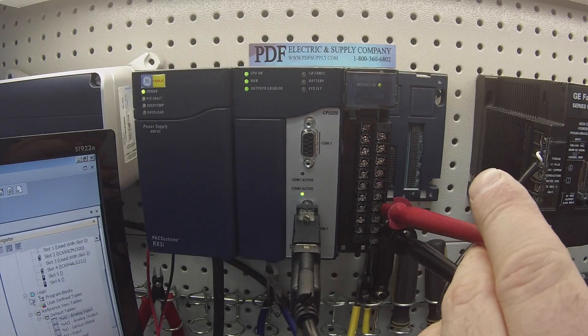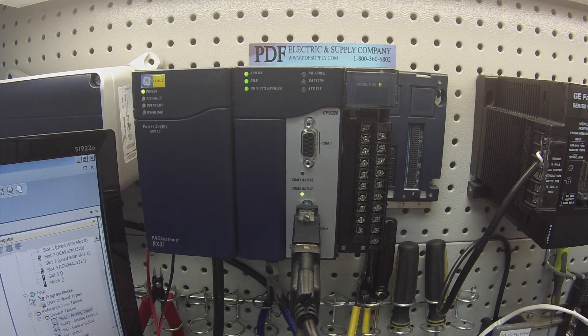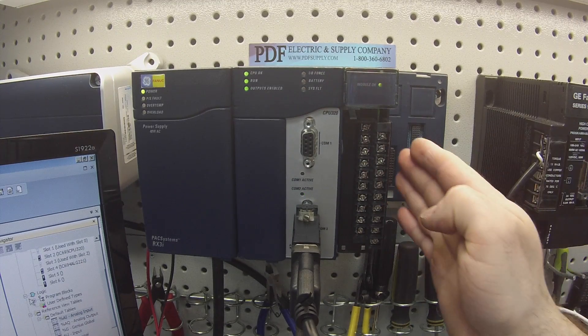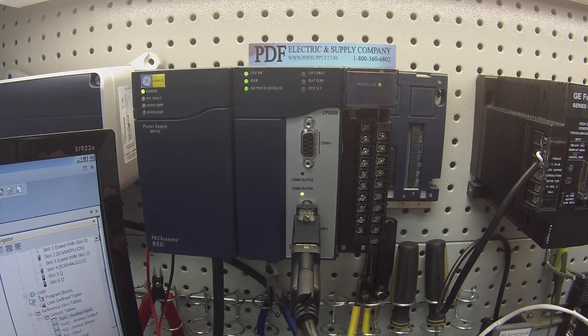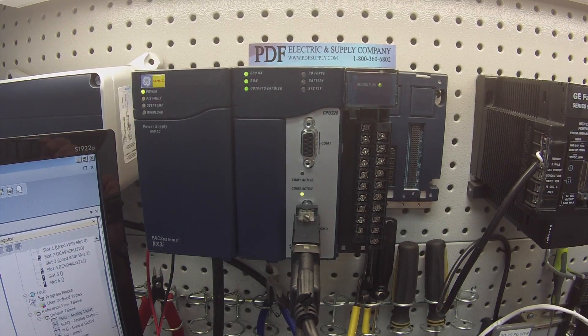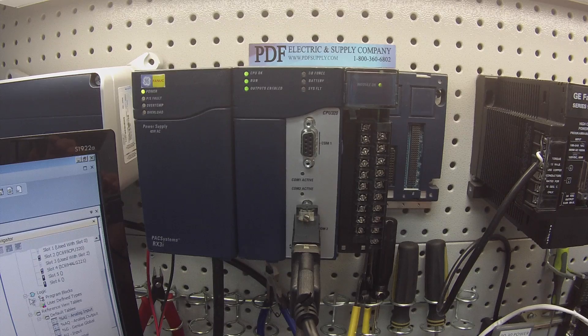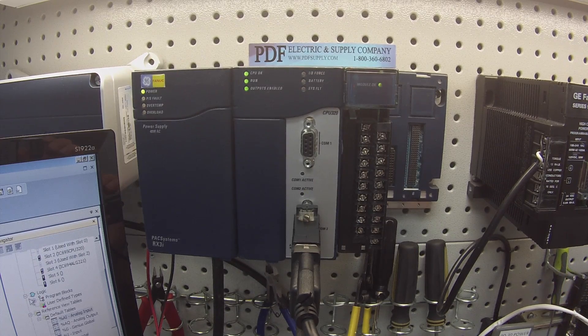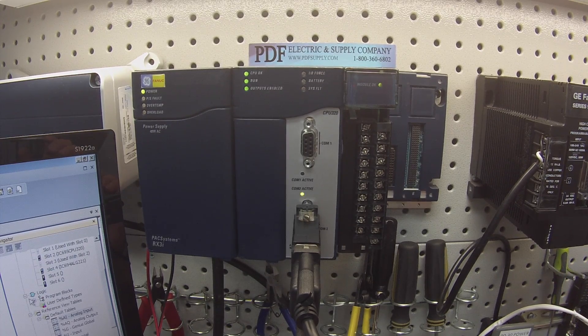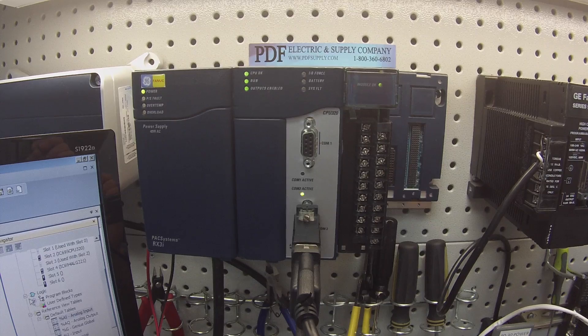Pretty simple. So again, just to recap things that you want to see, make sure that you power your rack with 24 volts the way it's required. Make sure that there's an OK light on once you do power it up, when the system's all powered up and the 24 volt power supply is powered up, you need to have a module OK light on.